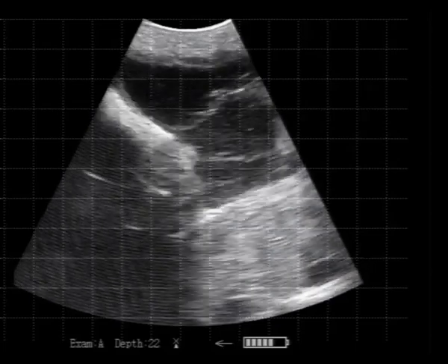Some opens might be more difficult to see. Let's recap what we did: we increased the overall gain, decreased the dynamic range to 30, increased the far gain to 30, lowered the frequency to 2.5 MHz, left the IP at IP2 but noted you can lower it to 1, and increased the depth of focus to 12.